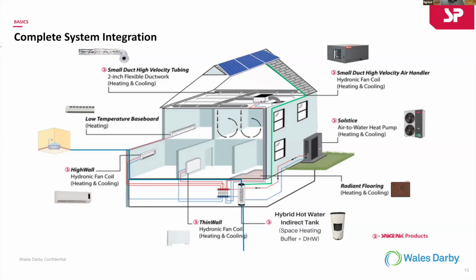Like I said, you can mix and match this. You can have your traditional baseboard. You can have radiant heating. If you want to use the old cast iron radiators in the house, you could do that. If you want to go more modern, with thin wall heaters, fan coil units, or wall units like the mini splits, you put them up on the wall. If you want to supply heating and cooling to those, you put those types of emitters in. But again, you can mix and match.